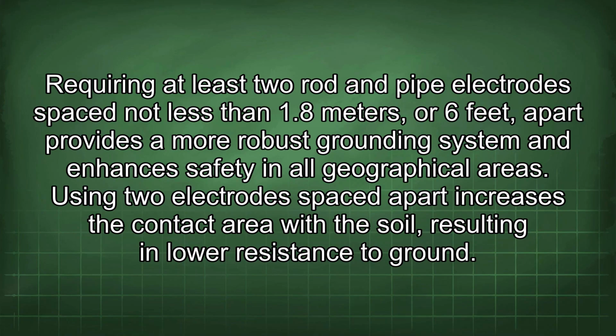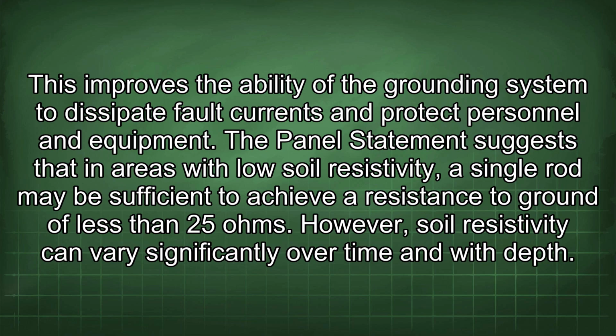Requiring at least 2 rod and pipe electrodes spaced not less than 1.8 meters or 6 feet apart provides a more robust grounding system and enhances safety in all geographical areas. Using 2 electrodes spaced apart increases the contact area with the soil, resulting in lower resistance to ground. This improves the ability of the grounding system to dissipate fault currents and protect personnel and equipment.